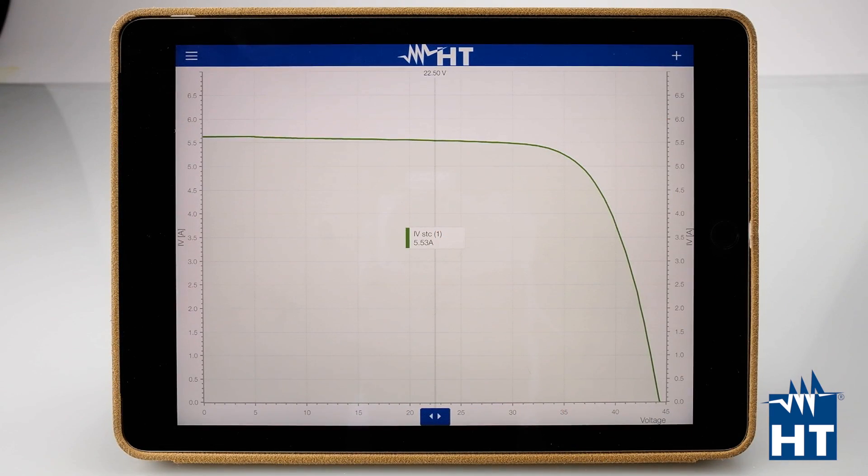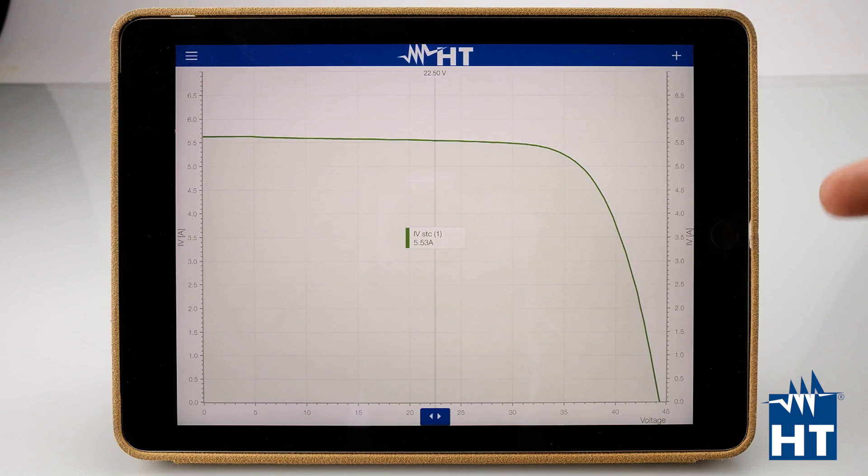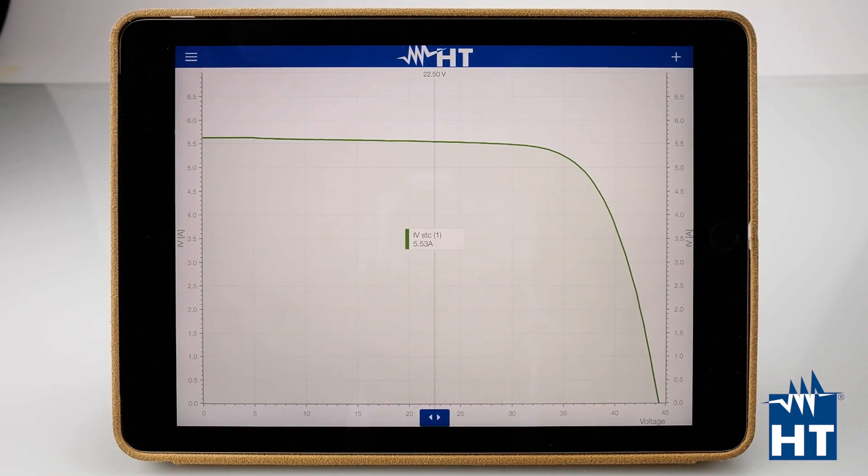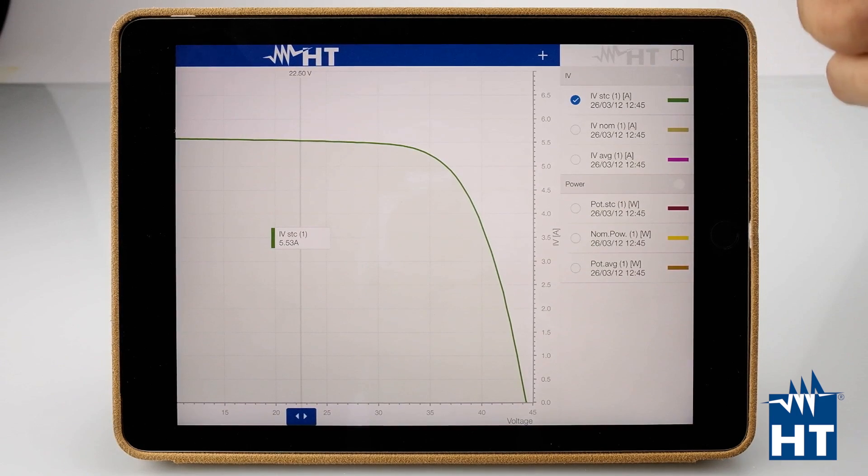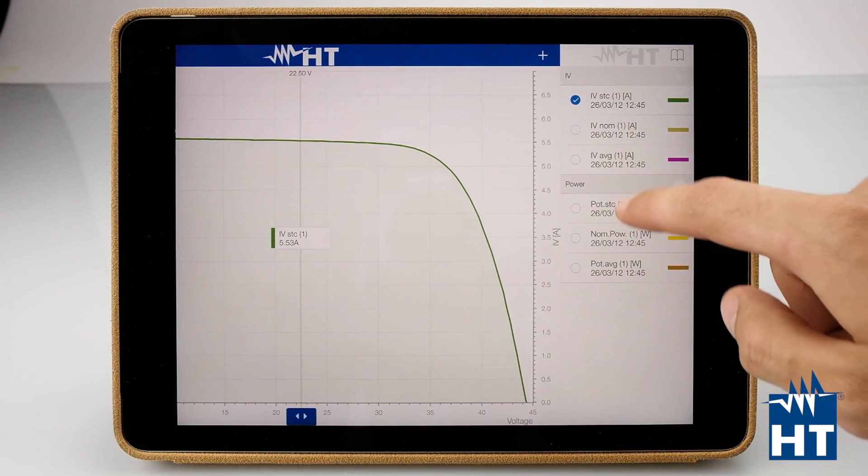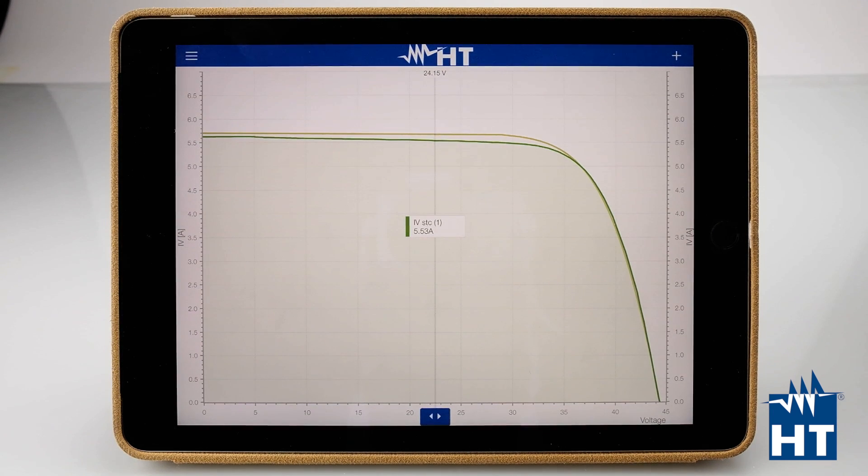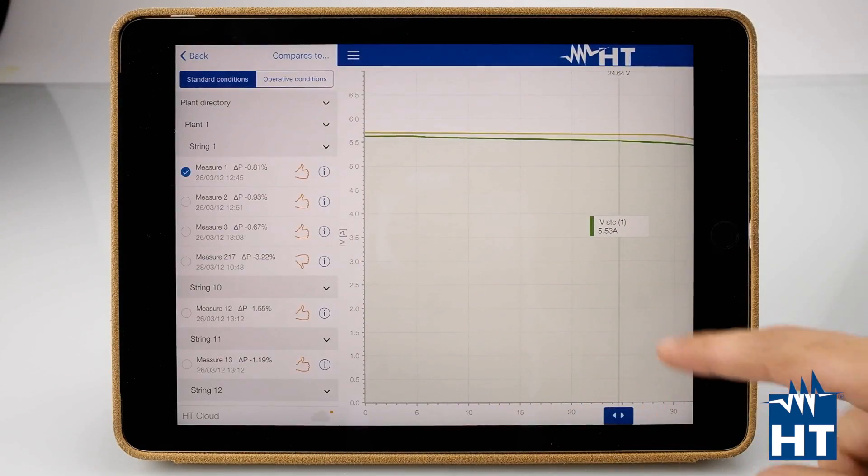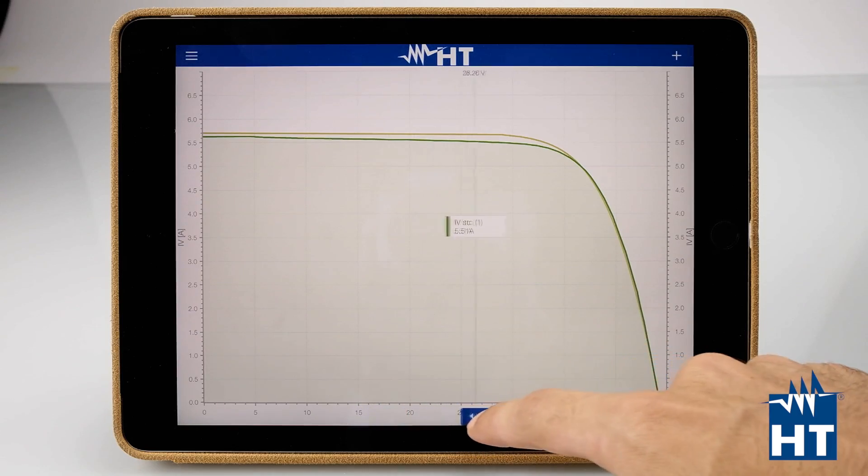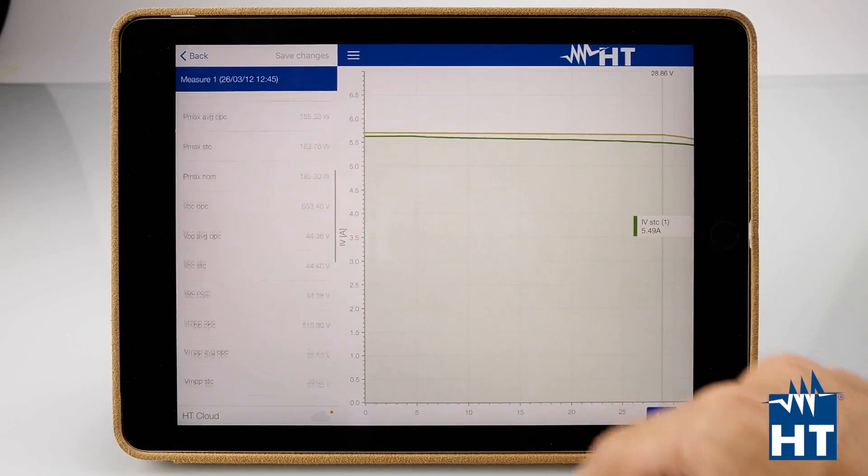IV STC is our IV curve measure already compared with the standard condition. So the calculation compared with the manufactured data is already done by the app. Here we have STC, which is this graph. Then we can put in the graph IV nominal, which is the nominal curve from the manufacturer without any calculation. As you can see, here we have some delta, some difference, that we can find values. We can move the cursor here and press I for info. Here we have all the data about the measure.